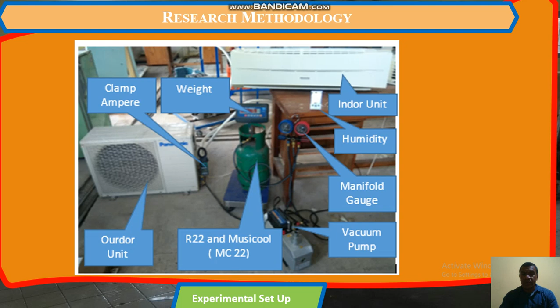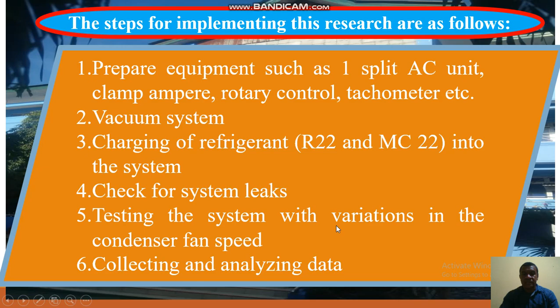The steps of implementing the research are as follows. At first, prepare equipment such as one AC split unit, clamp ampere to know the consumption of ampere, rotary control to control the speed of the condenser fan, tachometer to know the RPM of the condenser, etc. We need to vacuum the system, we need charging of refrigerant, R22 and MC22, check the system for leaks, test the system with variation in the condenser fan speed, and collect and analyze data.